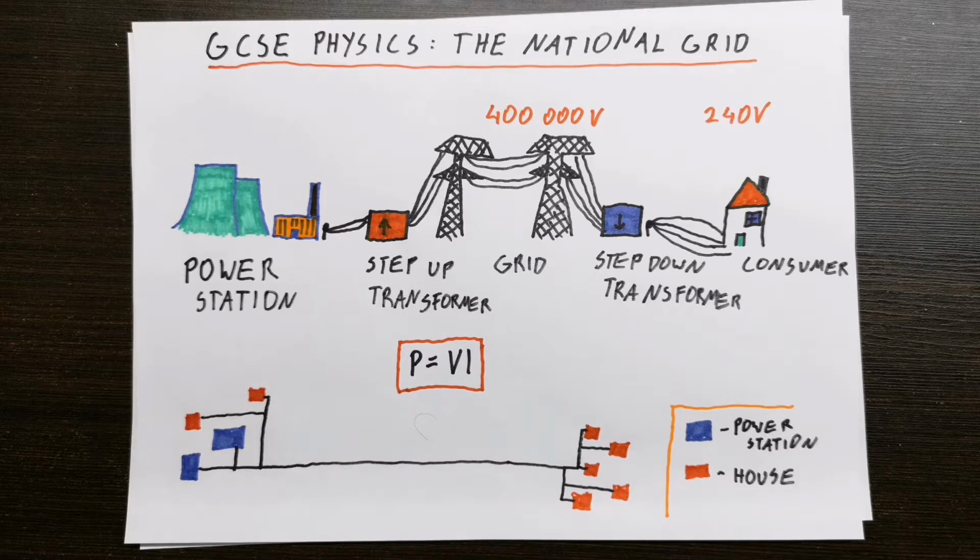So basically every point at which we have a step-up transformer, it will step up the voltage to 400,000 volts. And that way we standardize everything. We keep everything the same across the grid. That's the voltage we use. So that, I remind you again, makes it so we are transferring large amounts of power whilst keeping the current low to prevent heating up of the cables.